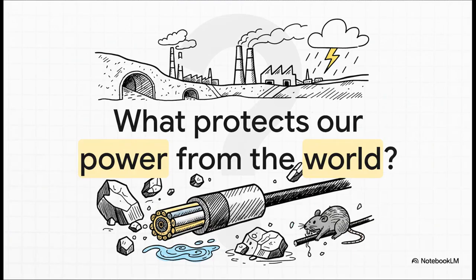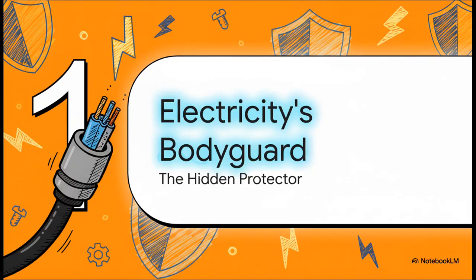Power cables, they don't just exist in some perfectly safe, clean environment. No way. They're buried in the dirt, run through massive industrial sites, and are constantly exposed to the elements. They have to deal with the threat of being hit by an excavator, crushed under immense pressure, flooded with moisture, even chewed on by rodents. So what's standing between all that chaos and a total blackout? Well, the answer is a really brilliant and, frankly, super rugged piece of engineering. You could say that our electricity has its own hidden bodyguard.